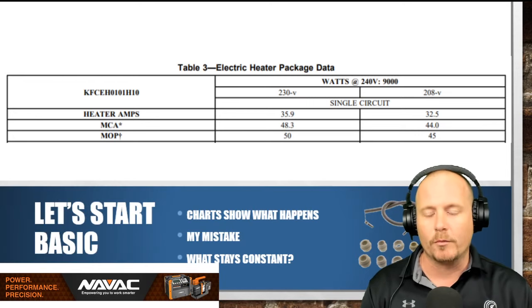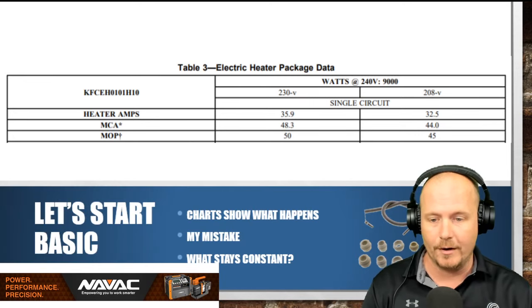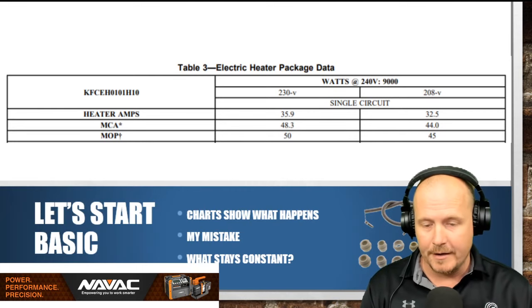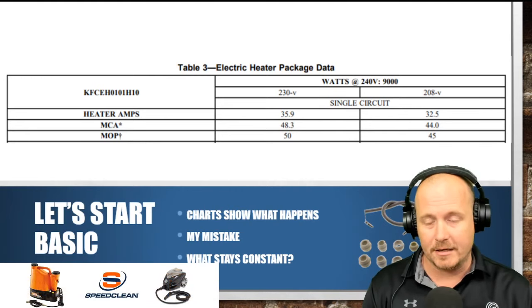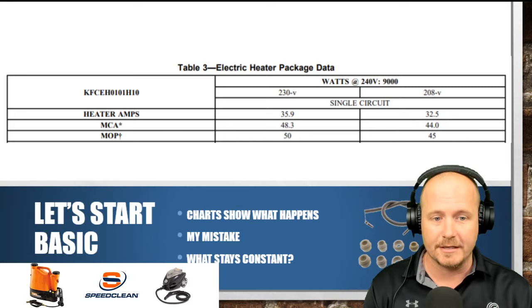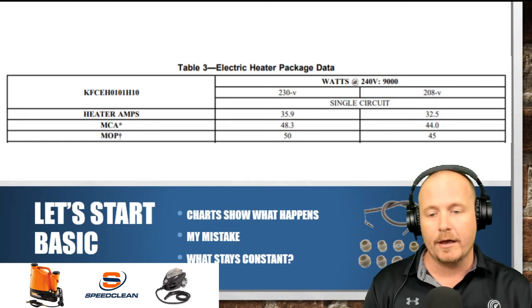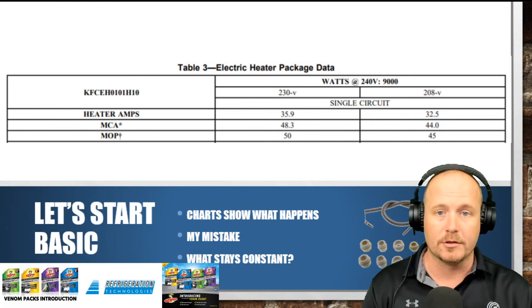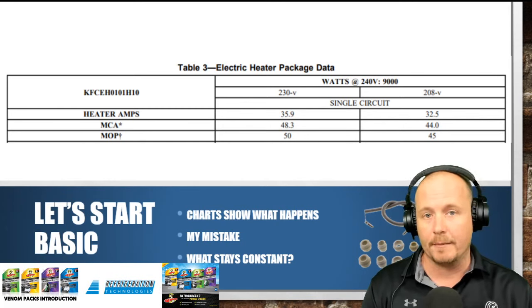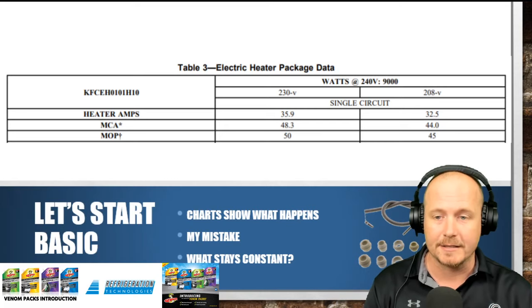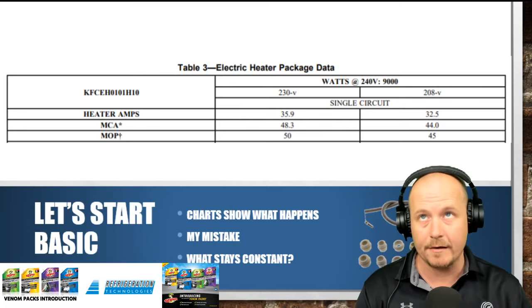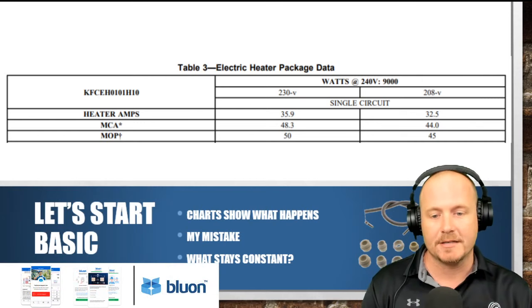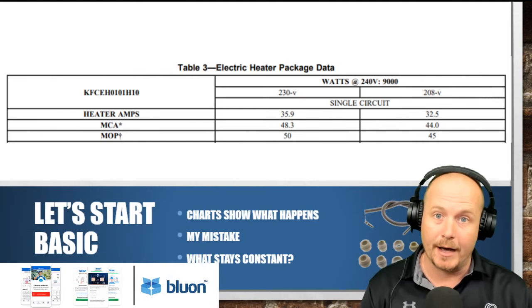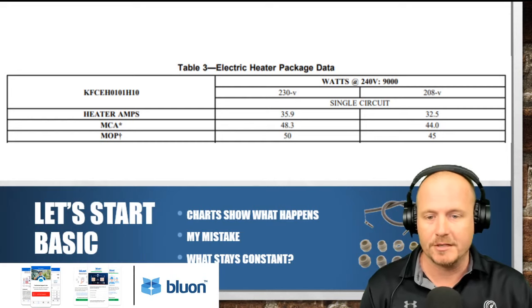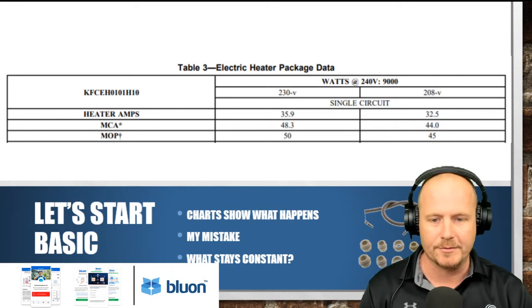So the question is, what really stays constant in a resistive load? On the face of it, it would seem like the resistance stays constant, and in this case, with a heat strip, the resistance is what stays pretty constant. In order to really calculate what happens when you change the voltage, you have to start with Ohm's law, by multiplying your resistance. It's E, voltage equals amps times ohms. So you start with your resistance and then do the math, which we'll do on the next slide.